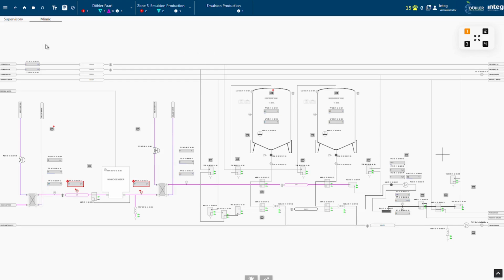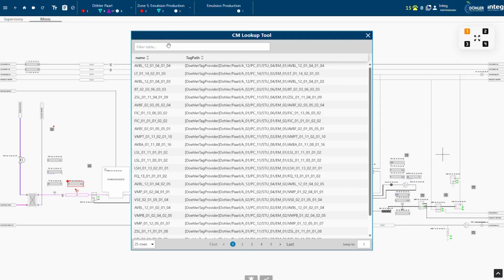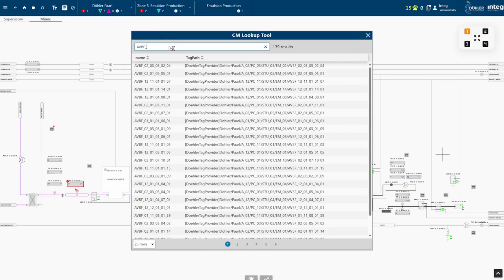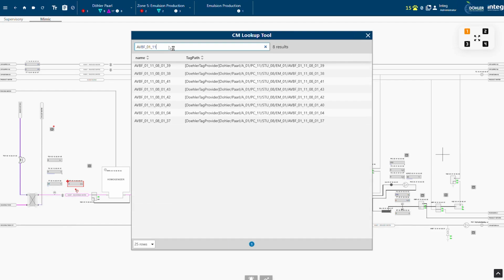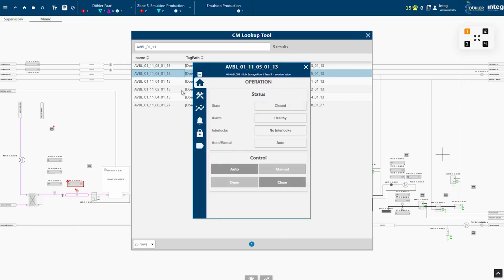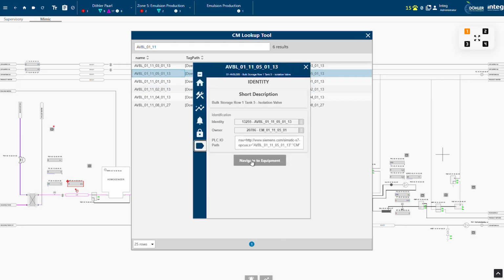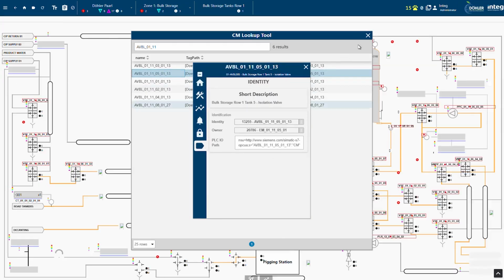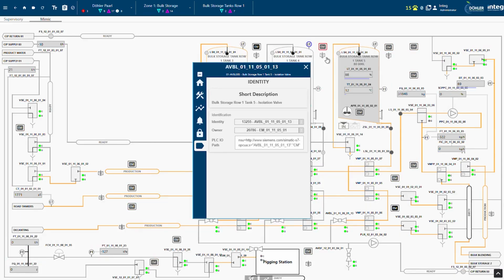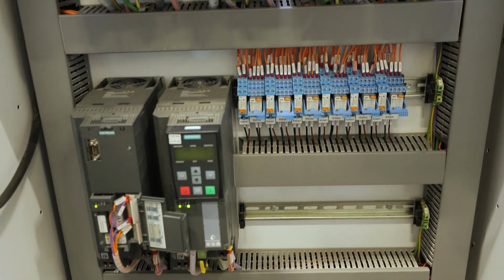The architecture of this plant in the beginning was a very standard setup with one gateway, but that changed quickly when we realized the number of tags required an additional gateway. We ended up with one master gateway where the Perspective module is installed, and a second, headless gateway for the second part of the facility. The facility comprises two sections, each on its own unique gateway, and each gateway communicates with its own central PLC.